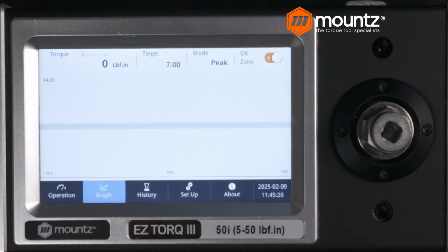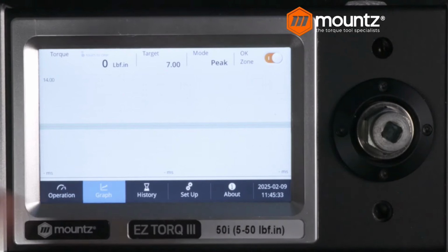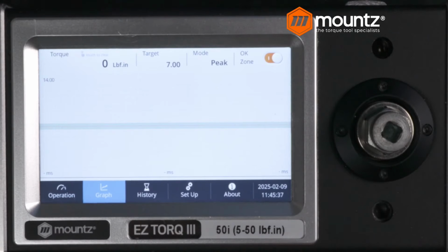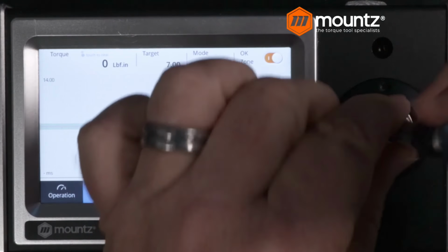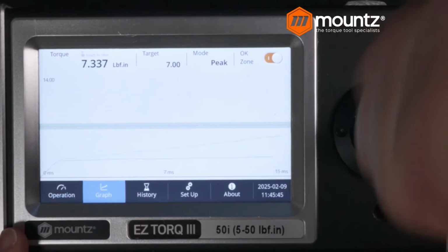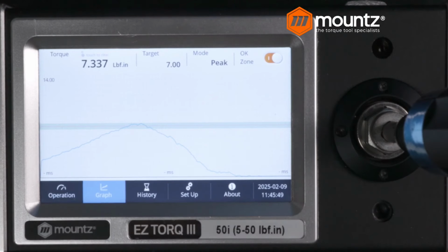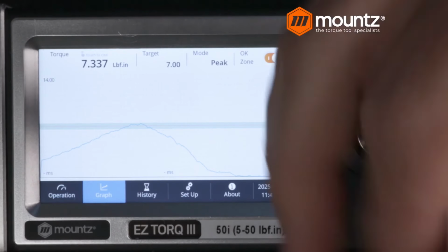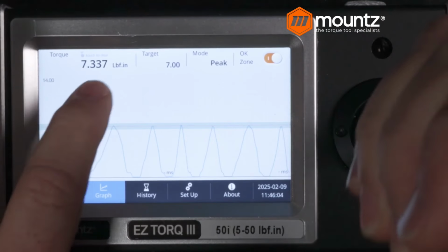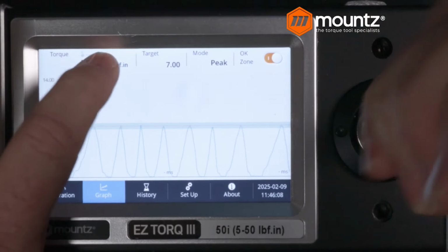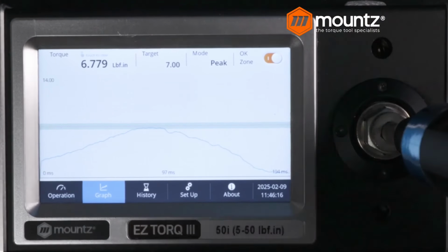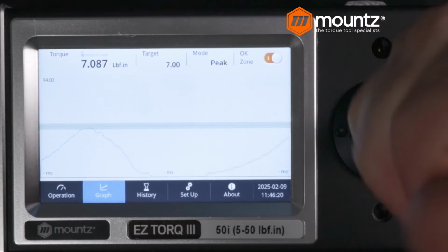So I'll use this basically when you do a calibration on a tool. You want to exercise that tool 5 to 10 times to make sure that the tool is ready to be calibrated. So we'll do that here using our graph function. As I apply load to the tool, you can see it's generating the graph. Everything within the green here is going to be acceptable limit for our tool. I'll just go ahead and run this a few times and we'll see what we get. Now you're not seeing any of the values change because I'm not clearing that, but I could clear it. Nevertheless, this is what we can do to exercise this tool.